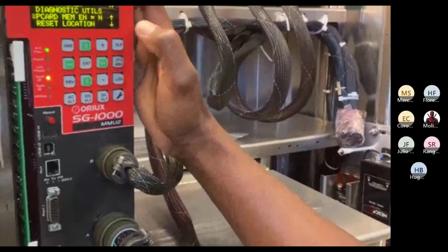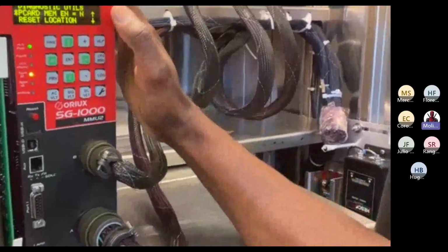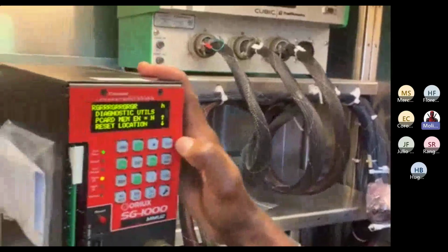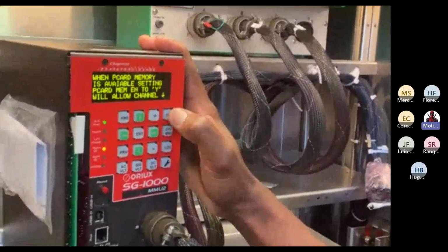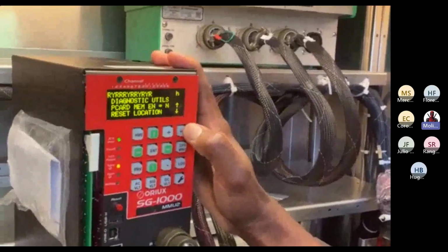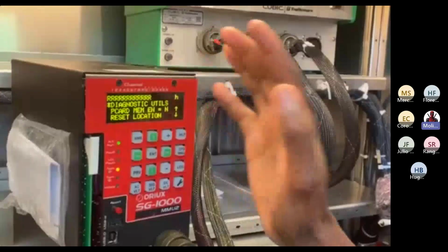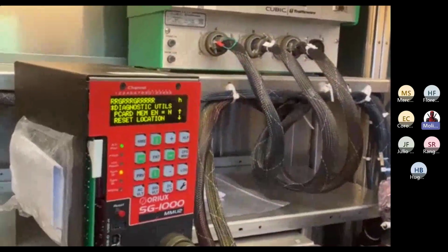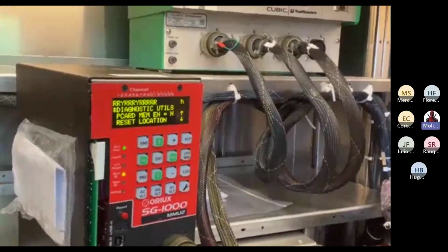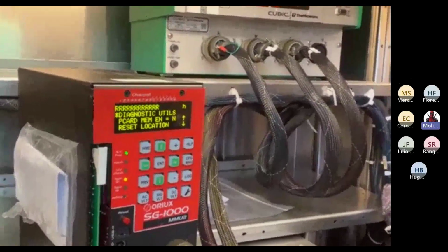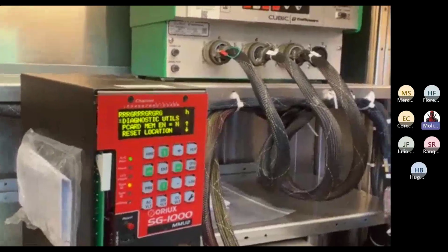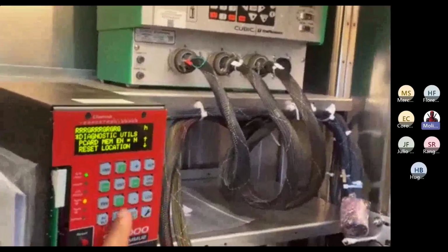I like this one. It's not bad. Right. Oh yeah, there we go. So I was talking about the P card memory. It's disabled. Well, it may be disabled because you have the non-memory card in there, or I think it's disabled by default. So if you turn that on, anything you change in the monitor is saved onto the card. So at any point you can pull that card, pop in a new monitor, and go to this menu. It'll actually ask you, do you want to change the settings to what's on the card, or change the card to what's on the unit? Right. And then you select, and boom, you just load the settings into the monitor.